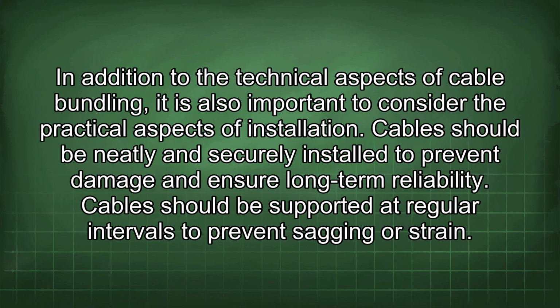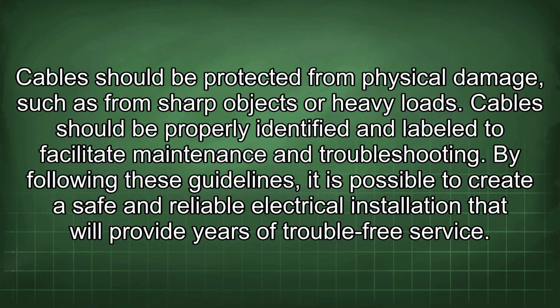In addition to the technical aspects of cable bundling, it is also important to consider the practical aspects of installation. Cables should be neatly and securely installed to prevent damage and ensure long-term reliability. Cables should be supported at regular intervals to prevent sagging or strain. Cables should be protected from physical damage, such as from sharp objects or heavy loads. Cables should be properly identified and labeled to facilitate maintenance and troubleshooting.